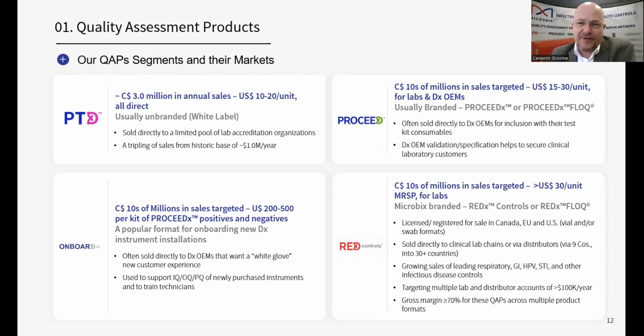And then an error can never persist across too many tests, which is incredibly important from a regulatory point of view to permit those instruments to be used outside of the lab setting, and to ensure that they're not causing more harm than good. And then the last category, the most regulated one, in the clinical labs themselves, where our test controls will literally bookend a shift of testing, so that you start the day with a known positive and a known negative to make sure that you pick up both of those accurately, and end the day the same way. And then for all the tests in the middle, you can have greater confidence that they were functioning properly.